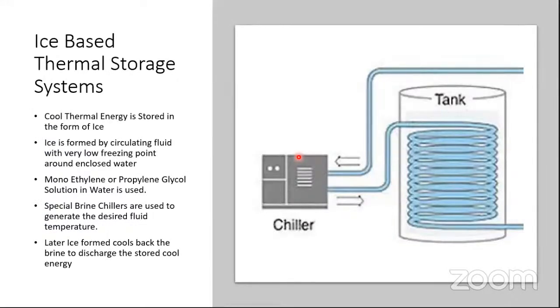Ice based thermal energy storage. We will now understand ice based thermal energy storage and its types. Here the cool thermal energy is stored in the form of ice. And ice is formed by circulating a fluid with a very low freezing point, called monoethylene glycol solution, which is circulated across the tank and forms ice inside the tank. Special brine chillers are used to generate the desired fluid temperature. If one has to form ice, there has to be a fluid which goes below the freezing point of water. That is the only thing that can make ice.